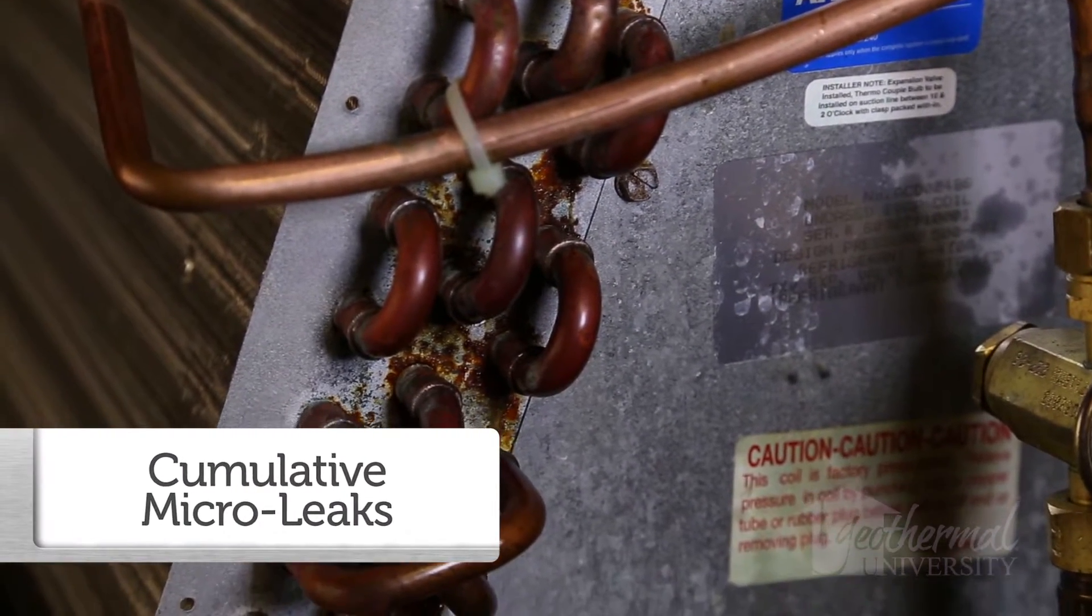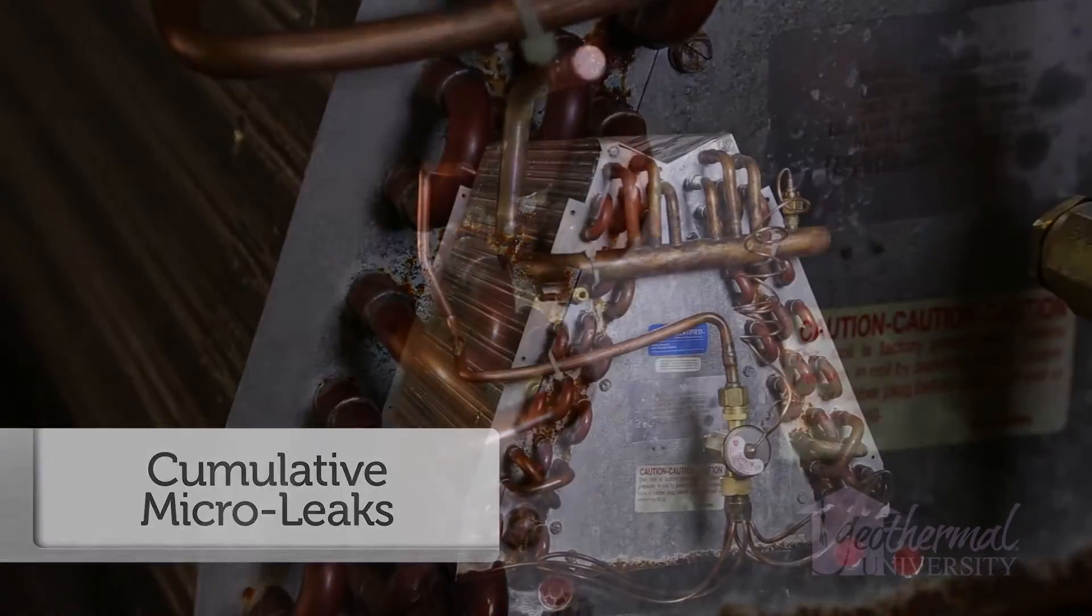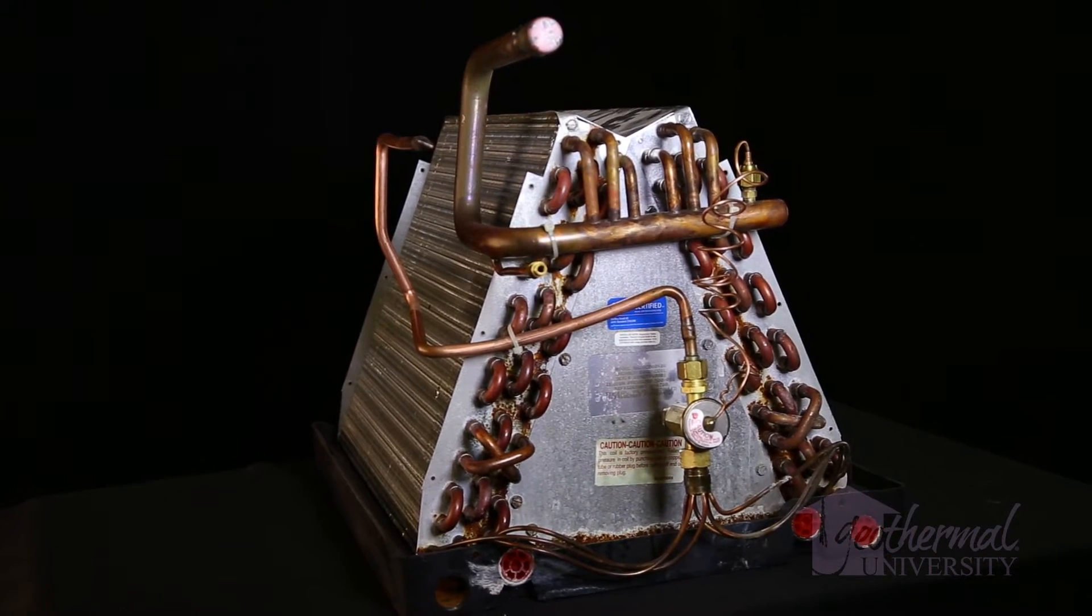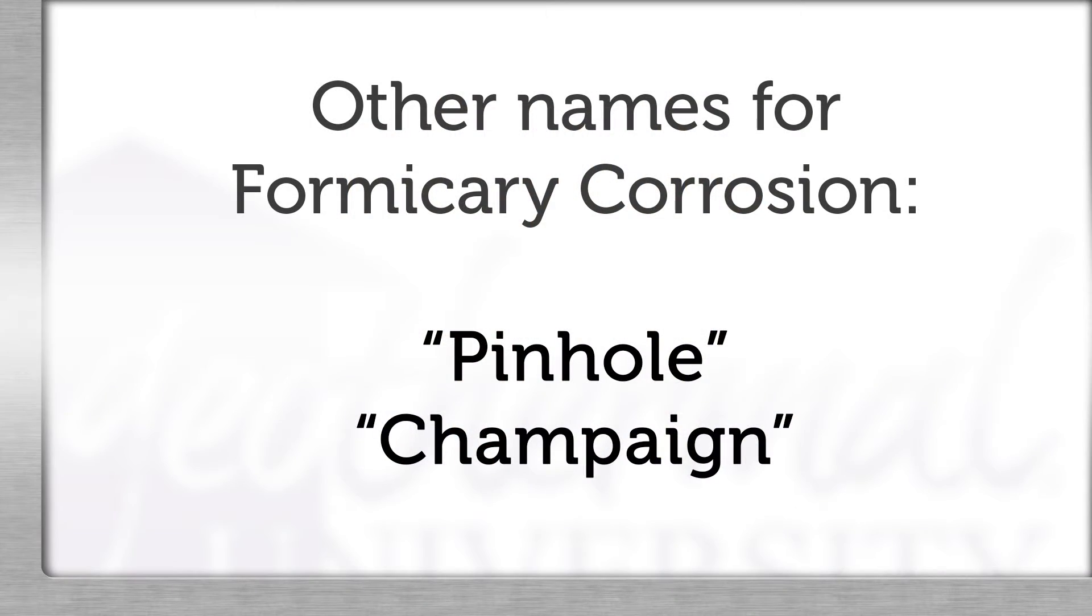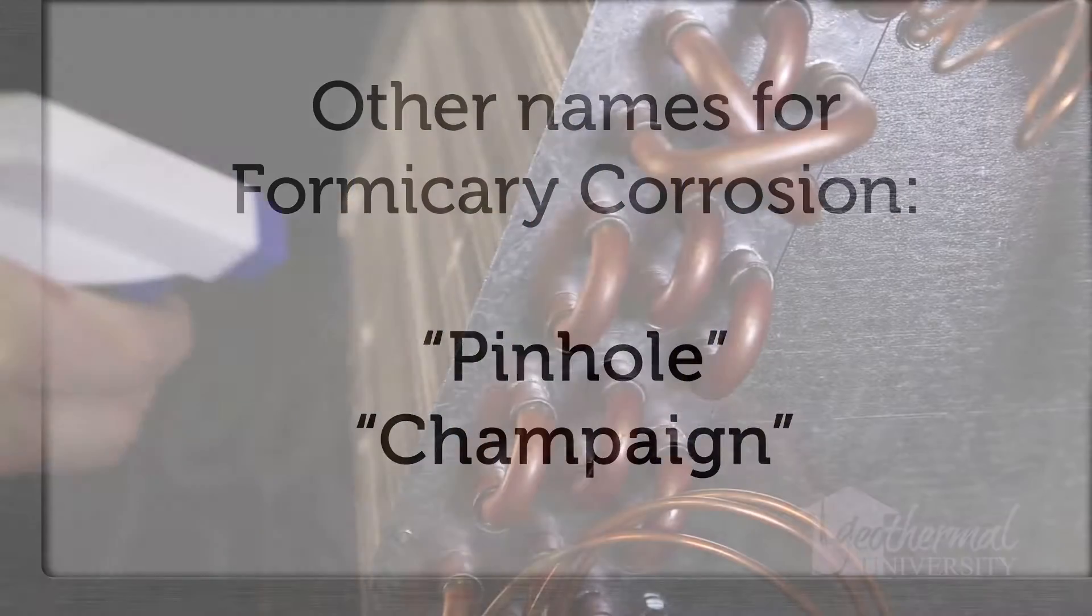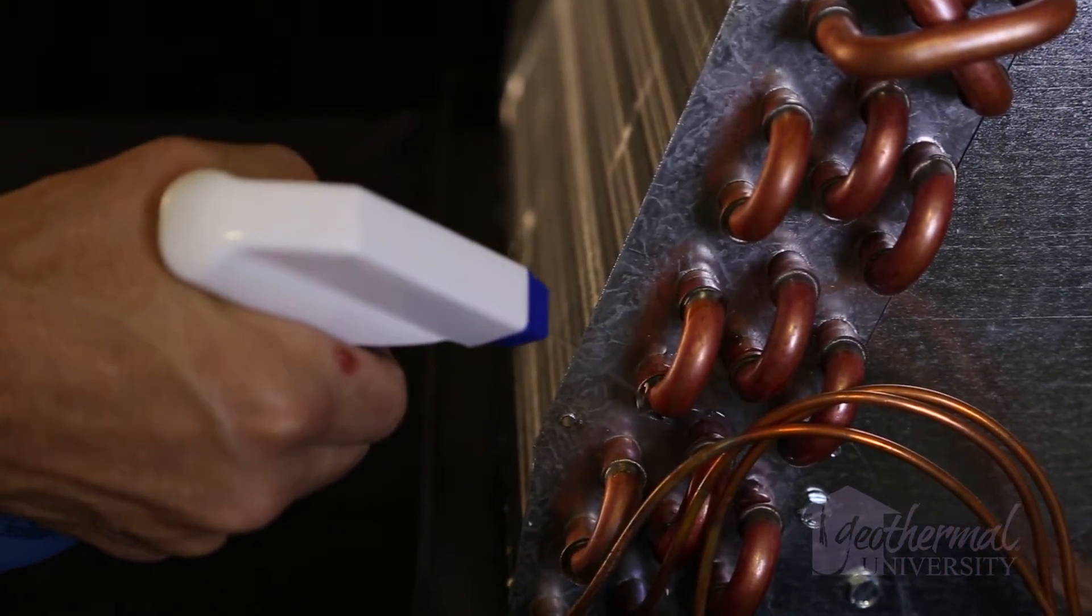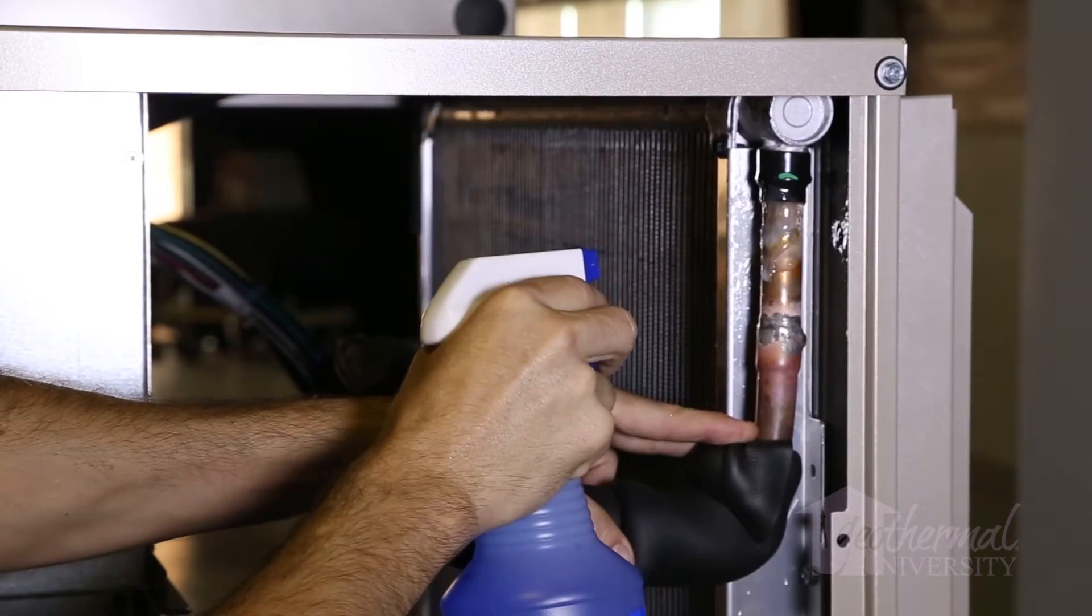Cumulative micro leaks are individual leaks that are too small to detect with standard tools. The total loss over many years of operation slightly reduces the initial gas charge. Pinhole or champagne leaks could be classified as micro leaks. Having knowledge of the classifications of leaks helps the technician understand the underlying cause of the leaks and helps them to troubleshoot a leaky unit.